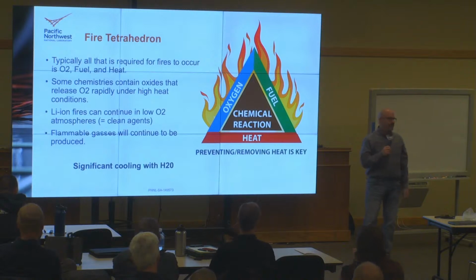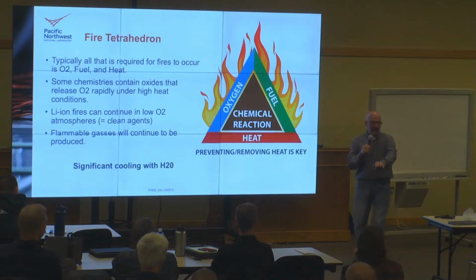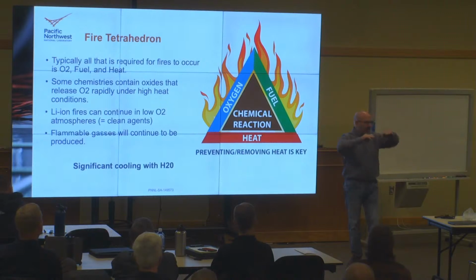And that's the issue. You'll even see demonstrations on YouTube where they'll have a couple of cells or a module sitting on a bench, put it into thermal runaway, and apply their agent. Well, that's an exposed module or exposed group of cells. Let's put it into a module that's covered with steel, inside a rack with 20 modules on top of it, and see how it works.